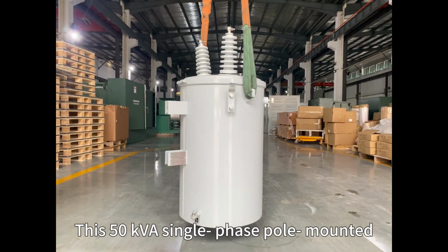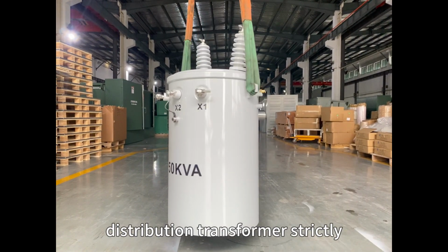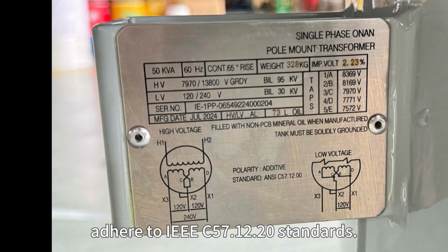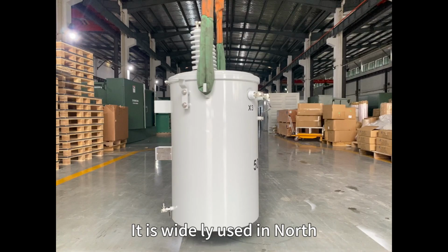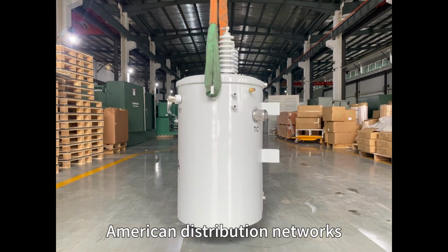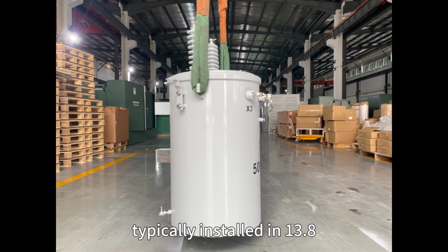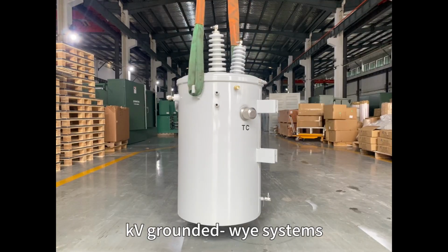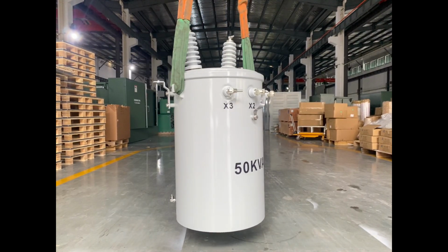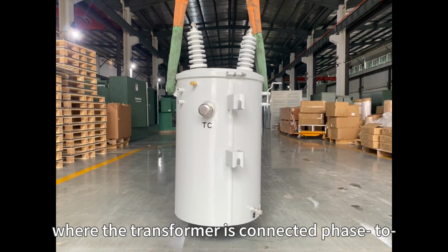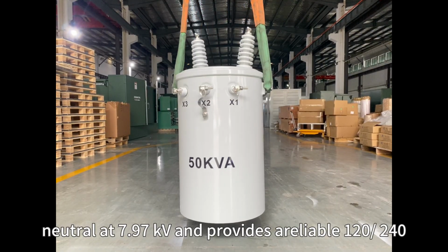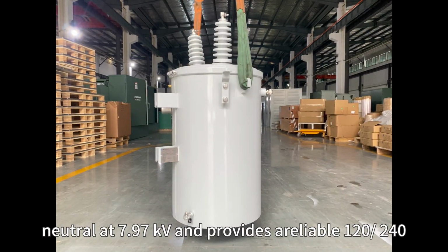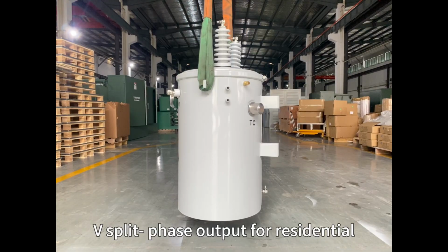This 50 kVA single-phase pole-mounted distribution transformer strictly adheres to IEEE C57.12.20 standards. It is widely used in North American distribution networks, typically installed in 13.8 kV grounded Y systems, where the transformer is connected phase to neutral at 7.97 kV and provides a reliable 120/240 V split phase output for residential and light commercial applications.